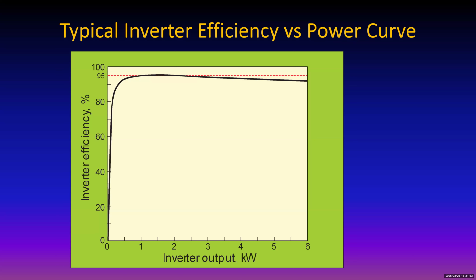And of course, an electronic inverter can get up to speed in a matter of a few milliseconds if you want it to, or it can be set to ramp up a little bit slower. There are different reasons, different cases. If you lose a generation source, you want to get another source to replace it as quickly as possible. And there are examples of a 100-megawatt system in Australia recovering in a matter of 100 milliseconds or so when a coal-fired plant was lost back in 2017 or 2018, I think it was early 2018. So inverters can be very handy when you lose a conventional generation source, or even if you lose an inverter source, another inverter can come on pretty fast.